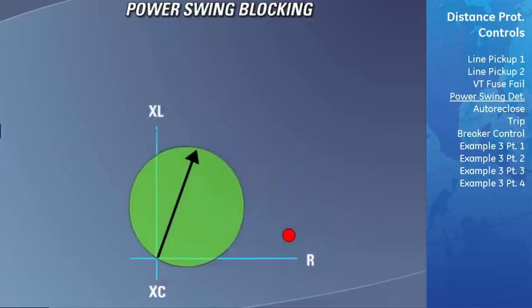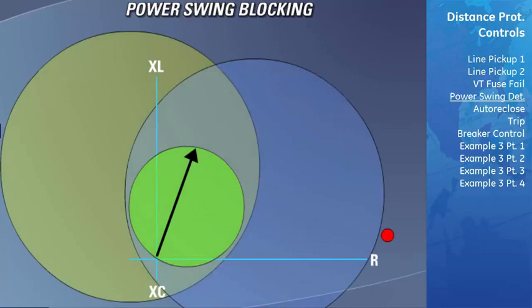zones from operating. The D60 detects power swings by establishing an area located around the zones of protection. If the D60 detects that the impedance of the system is located in this area for an extended period of time, it knows that this is a power swing and that the distance protection needs to be blocked. If this swing were a real fault that entered the power swing blocking area, it would have moved very fast and entered the zone of protection. The impedance would not have been in the blocking zone long enough for the blocking time to expire.